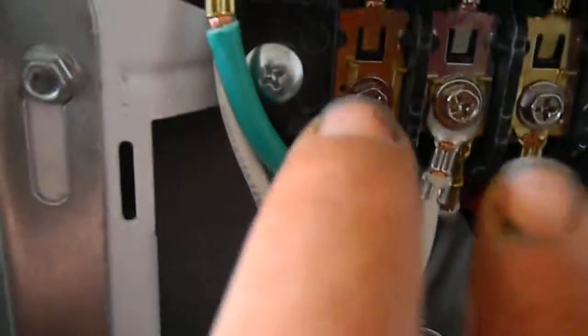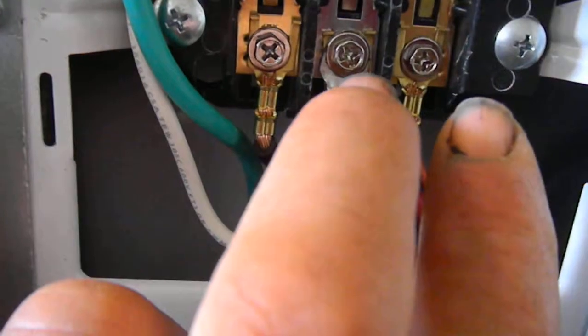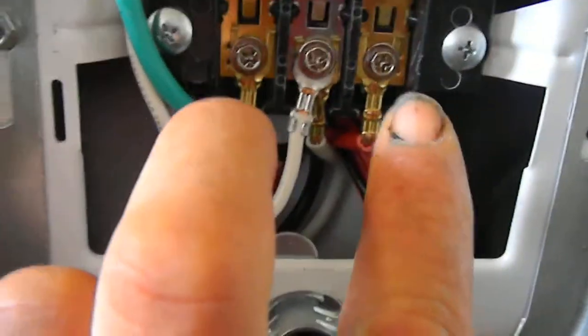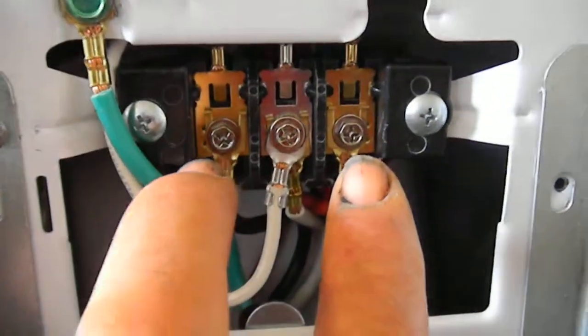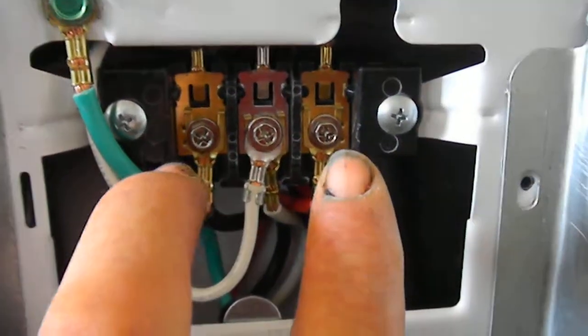So you need to have 220 volts across these two. If you have 110 here and 110 here, that's not good enough. You need to check across these two and get 220.